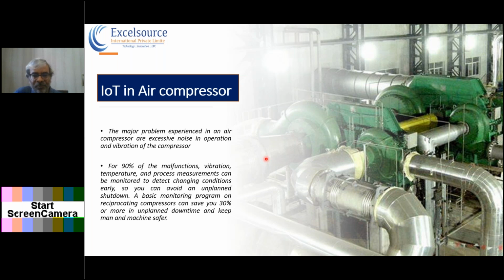We will be able to optimize the air pressure requirement based on monitoring the pressure at the outlet of the air compressors. And if we have multiple air compressors installed, we can build an algorithm to see which is the most efficient compressor to keep up and running, while the others are kept as standby. That optimizes energy consumption during normal plant operations, and the standby compressor is only used when peak demand comes, or when a shutdown or breakdown comes in the plant, for emergency usage.